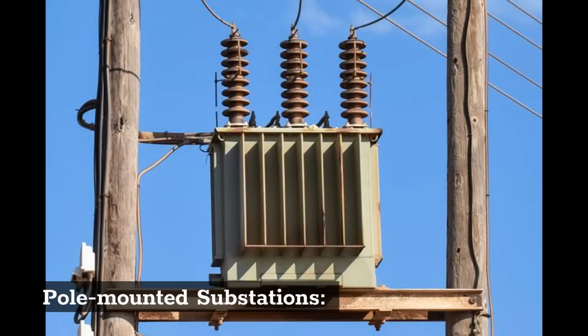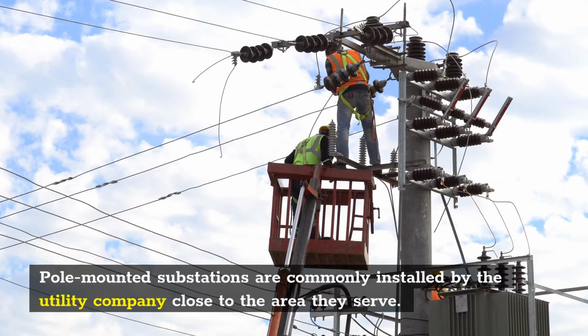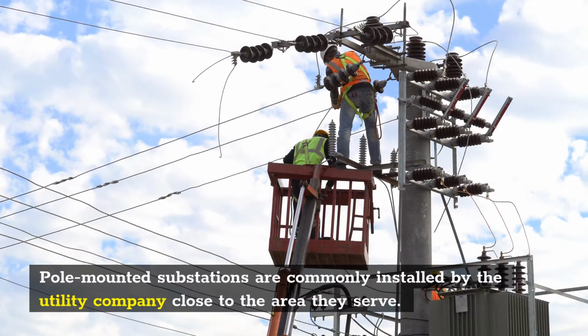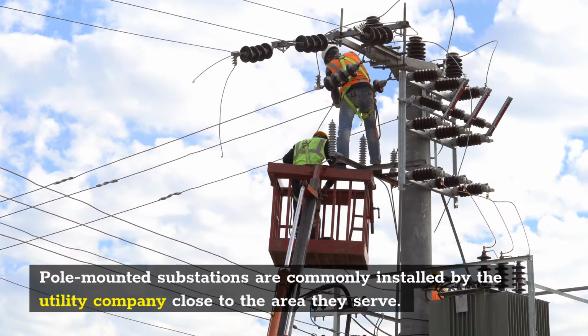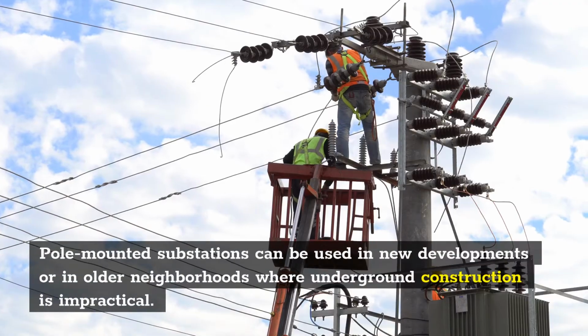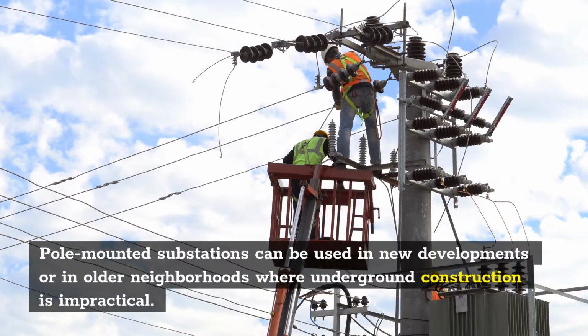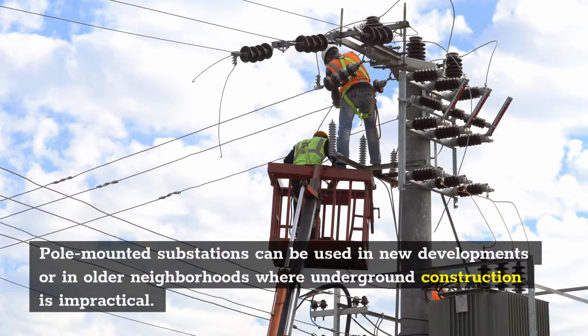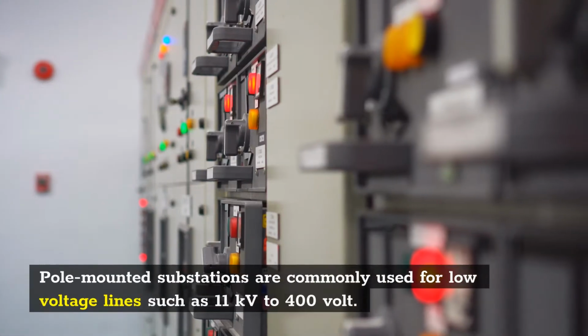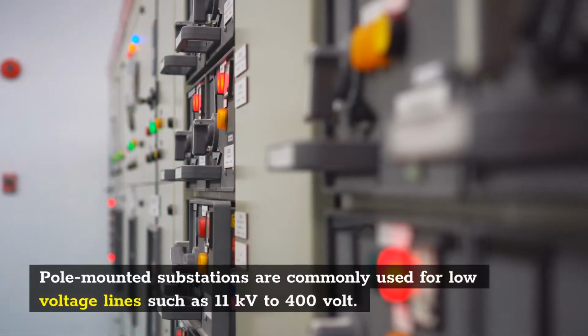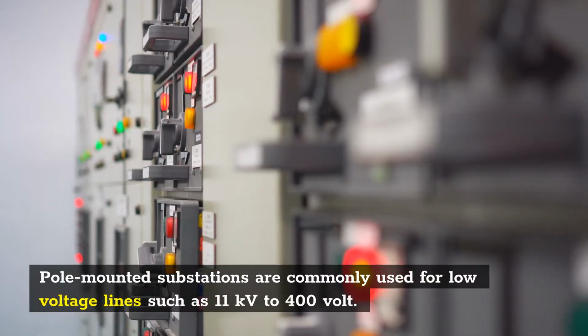Pole-mounted substations. Pole-mounted substations are commonly installed by the utility company close to the area they serve. Pole-mounted substations can be used in new developments or in older neighborhoods where underground construction is impractical. Pole-mounted substations are commonly used for low-voltage lines such as 11 kV to 400 V.